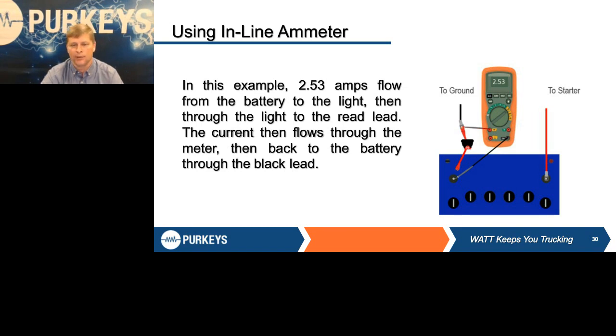I say that to reinforce—if you left a ground cable connected without noticing, you won't get an accurate reading because current will go through that other cable you didn't disconnect. So I'm looking at my meter right now, everything's supposed to be off, and I still have a 2.5 amp load. Am I done? No, all I've done is confirm that I do have a parasitic load here.